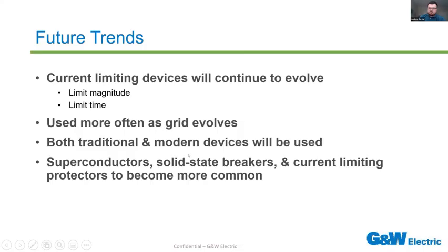So, in conclusion, going over some future trends that I anticipate seeing, these current limiting devices are going to continue to evolve. They're going to limit magnitude to a greater extent. They're going to limit time to a greater extent. You're going to see them used a lot more extensively as the grid evolves. You're going to see traditional and these modern devices used. Superconductors, solid state breakers, and current limiting protectors will become more common. You may not see them all, depending on what part of the grid you work on, but generally speaking, they are going to become much more common as time goes on.